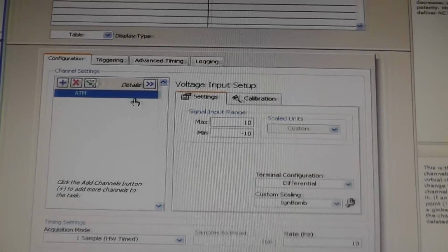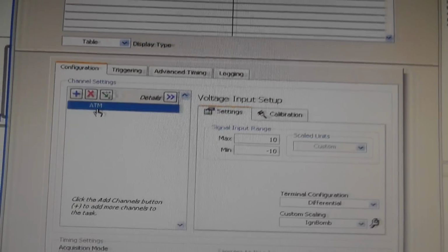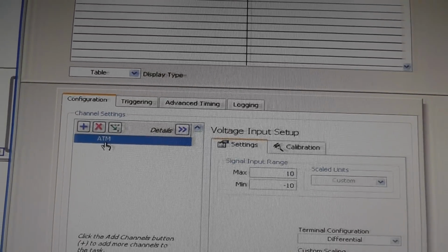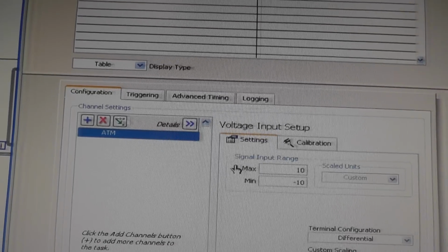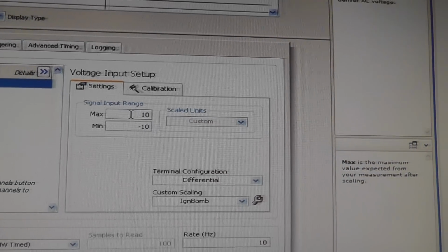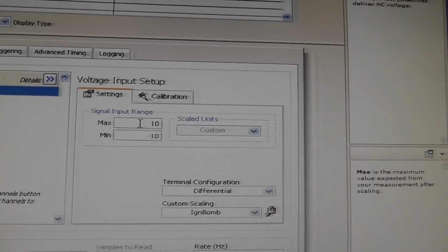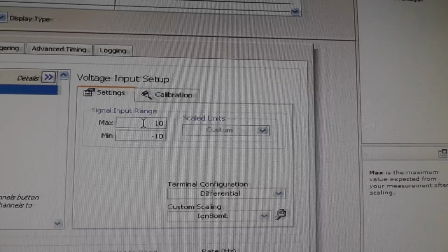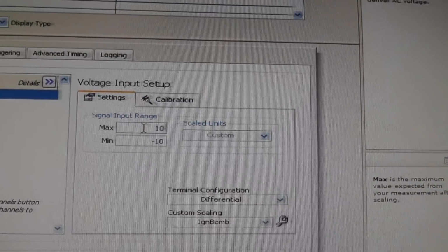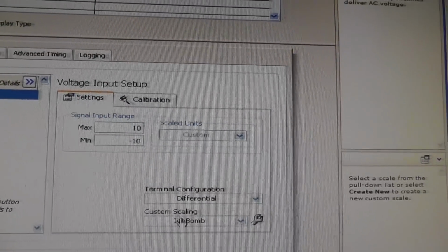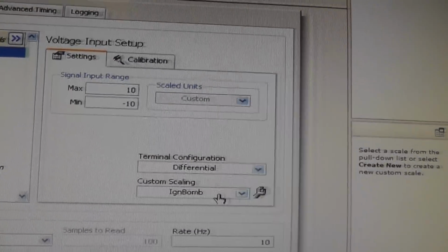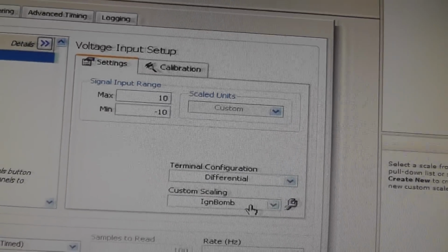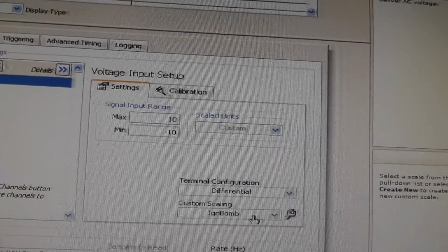Really all it's reading here is the pressure transducer, which is ATM for atmospheres, that's the units we're reading. Maximum and minimum voltages, so it's 10 volt max, negative 10 volt minimum, depending on how you calibrate it. It's all plotted through a graph here with a scale we set up for voltage, how much voltage equals how many atmospheres.